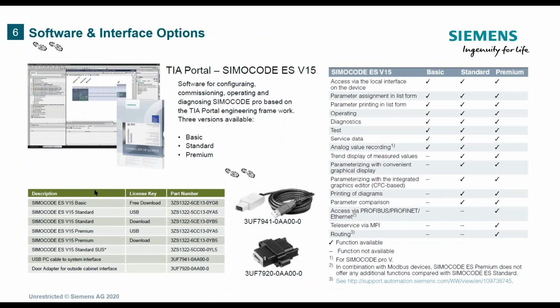Okay, software-wise. I've listed here TIA Portal V15. We are up to version 16 now with TIA Portal. If you've not worked with it at all, it is our all-inclusive software that programs our PLCs, our HMIs, our drives, our Simocodes, our soft starters, and any other field devices that we have, like Profinet push buttons and so forth. The reason I didn't put V16 in here is I want to emphasize something. If you have a customer, or if you are a customer, that already has Simocode software for older versions of TIA Portal, you don't need to buy any license.